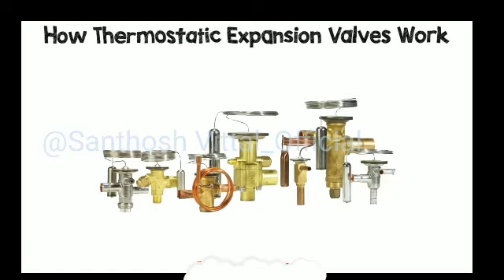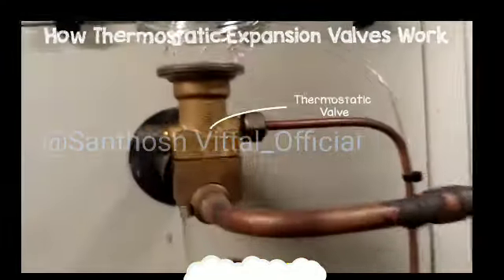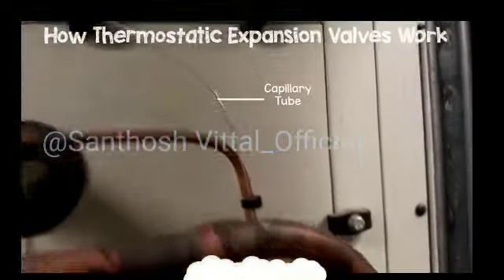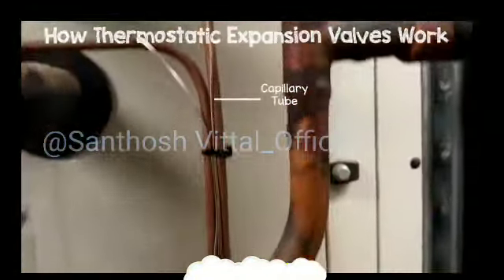In fact, let's show you a real world example. So this is the setup for an air handling unit, or AHU, and it has two expansion valves because it has a large cooling coil. The valve sits on the outside of the AHU at the evaporator entrance, and it meters the refrigerant flowing into it. We'll have a look exactly how this works shortly, but you can see here the capillary tube runs from the power head on the top of the valve all the way down to the sensing bulb, which is located at the evaporator exit, and that is measuring the temperature of the superheat.